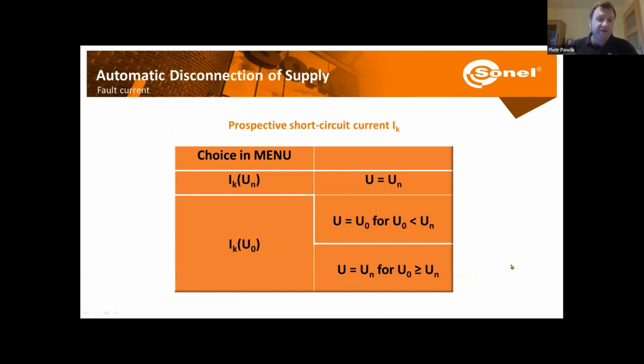Okay, now further on, the meters can automatically calculate for us the value of fault currents. But what value of voltage shall we use? Because to calculate the fault current, we need to know the value of supply voltage and the measured value of fault loop impedance. The impedance is just measured, and the supply voltage we can select either UN, so the nominal voltage, which typically in India is 230 volts, or U0, which is the actual measured value of the voltage.